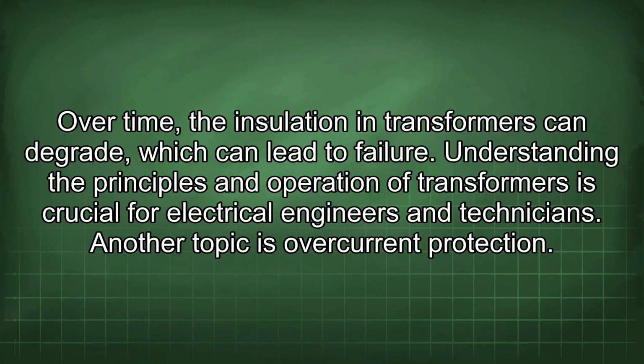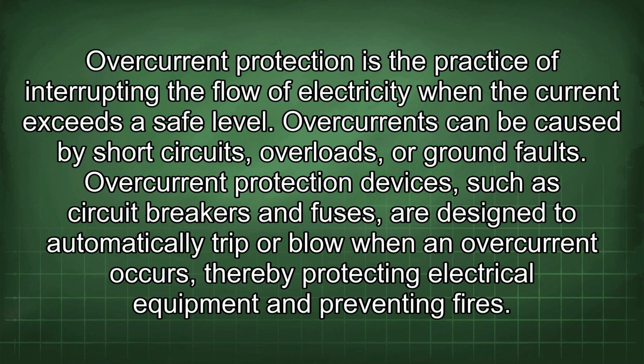Another topic is overcurrent protection. Overcurrent protection is the practice of interrupting the flow of electricity when the current exceeds a safe level. Overcurrents can be caused by short circuits, overloads, or ground faults. Overcurrent protection devices, such as circuit breakers and fuses, are designed to automatically trip or blow when an overcurrent occurs, thereby protecting electrical equipment and preventing fires.